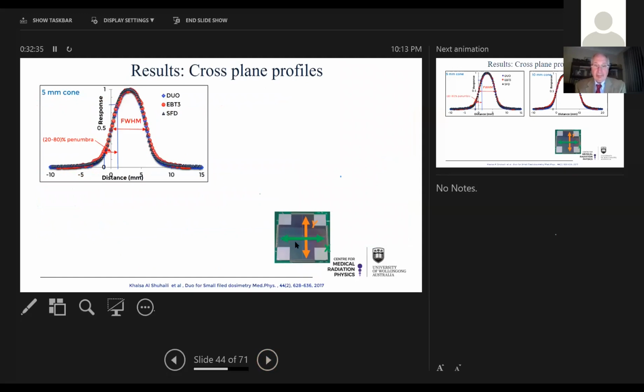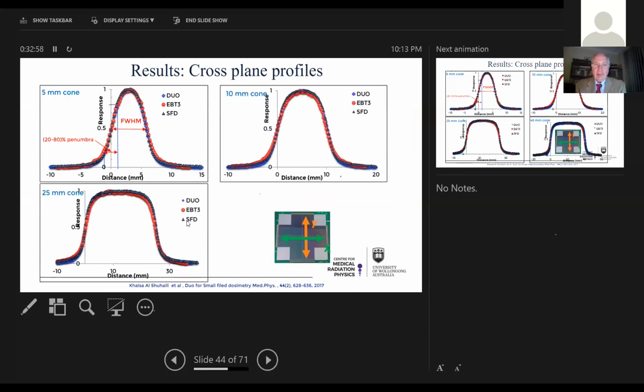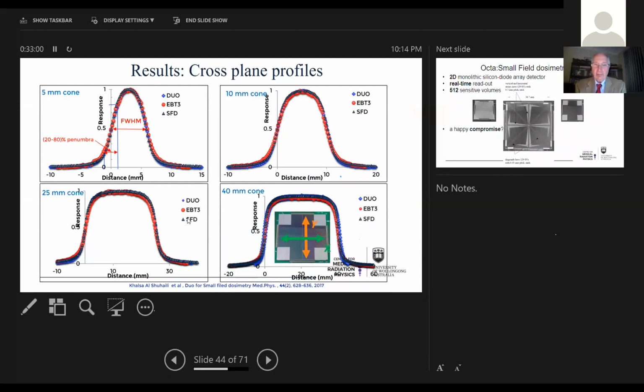You can remember the duo detector with 2 orthogonal pixel arrays with a 0.2 millimeter spatial resolution, where you can get the profile of the beam immediately. You can see a 5 millimeter cone. We're getting the profile within 5 seconds, and it's a beautiful agreement with chromic film. The same for the 10 millimeter cone, 25 millimeter cone, 40 millimeter cone. So it's implemented clinically now, and people are quite happy with this instrumentation, which allows you daily QA for cones.